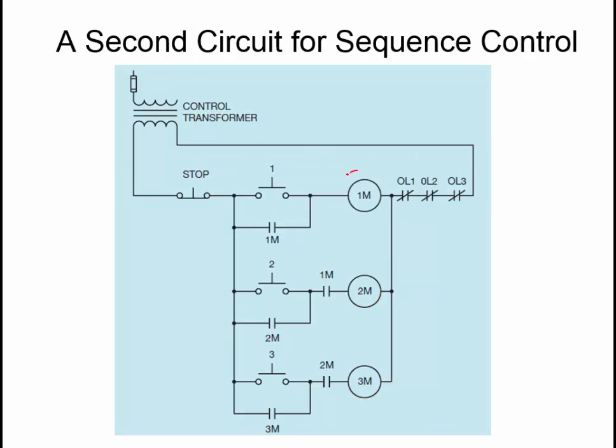In this way we take an extra auxiliary contact. So here's M1, and now we have two normally open contacts on that contactor, on that big motor starter. This is AND logic, so it's telling you I've got to press this start button AND I need to have motor 1 running to get motor 2 to start. And this is the same setup down here.